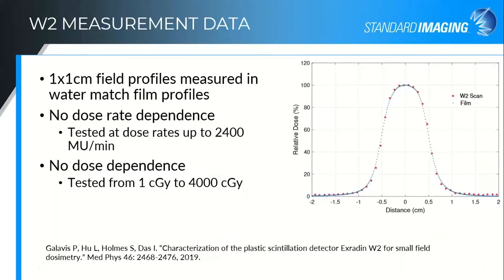Some examples from when the W2 was first launched: a publication from Paulina Galavis and the group at NYU Langone compared the W2 with the W1 for physical characteristics and behavior of the fiber. As expected, none of the behaviors changed — dose and dose rate dependencies were as expected. They also compared scanning measurements of small fields with film, showing a one centimeter field scanned with the W2 compared with GafChromic film, and they got excellent agreement.